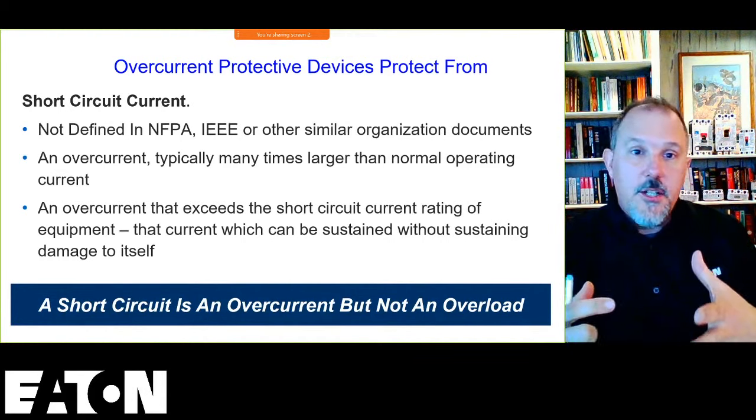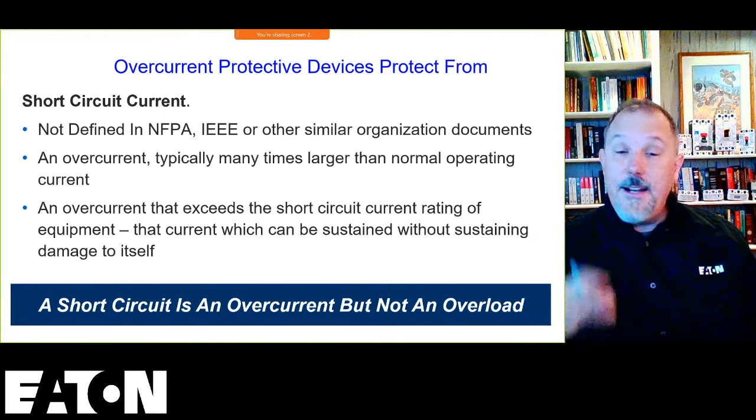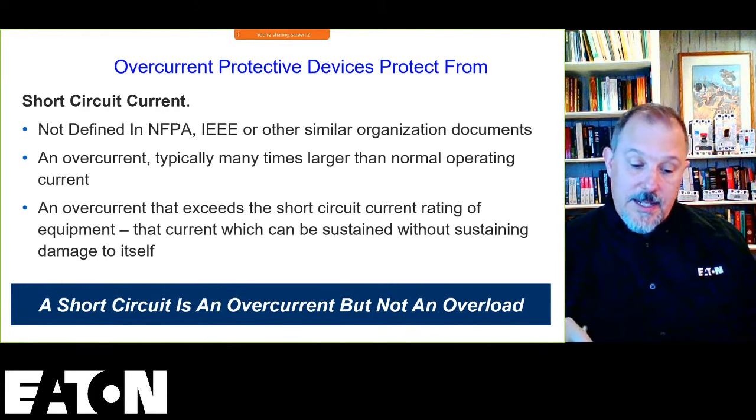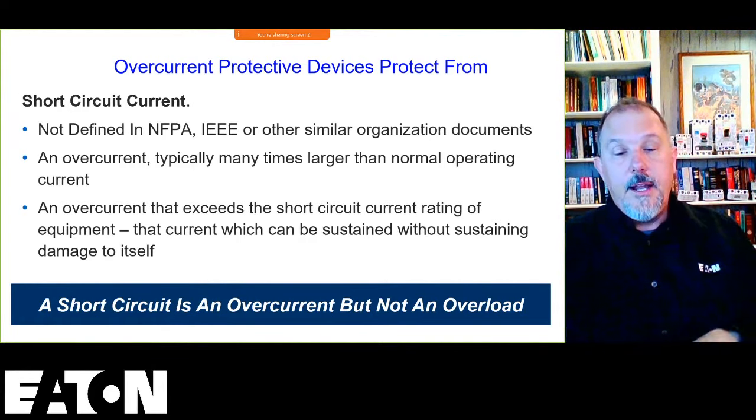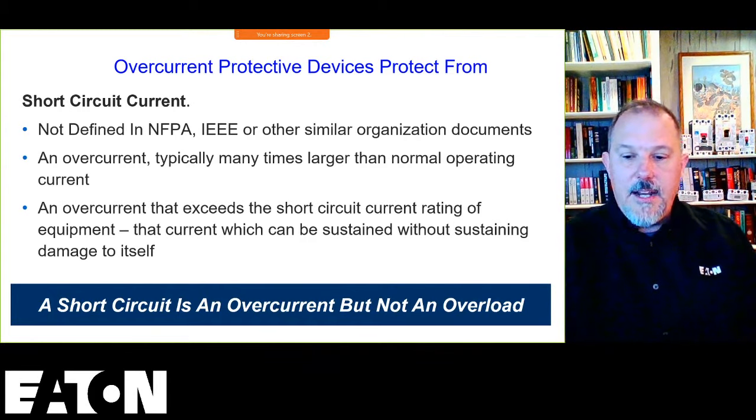Now, short circuit current is not defined in the National Electrical Code. We entered a new definition in the 2020 cycle, which is called fault current. A fault current is the current delivered to a point on the system during a short circuit condition. You think about it as going outside of the normal path.